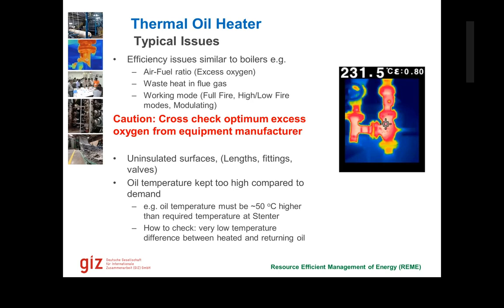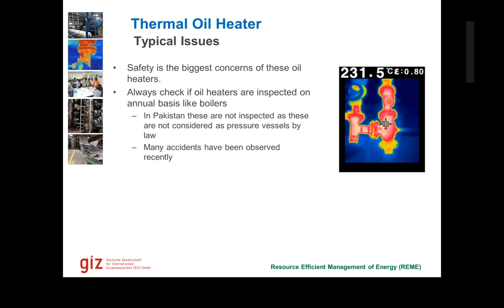So that is what we also need to look at. And then we already discussed this point of how much additional degrees we need in thermal oil heaters, and also having a look at how much temperature the thermal oil is giving up while returning back. If at the oil heater we're only getting 2, 3, 4, or 5 degrees of delta T, that means we are overheating the oil. Then safety, because it is a pressure vessel, but unfortunately these are not inspected as pressure vessels, because in Pakistan they do not consider oil heaters by law as pressure vessels, and we have seen many accidents taking place in a few years.